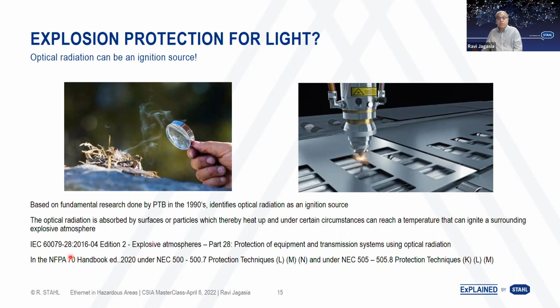The standard was published in 2016, the latest one. The earliest was in 2006, where they defined this protection of equipment and transmission systems using optical radiation. In the US, the NFPA 70 under the aegis of NEC 500 adopted these protections under 3 different classifications, the L, M, and N, and under 505, also under 505.8, they also adapted it as K, L, and M.